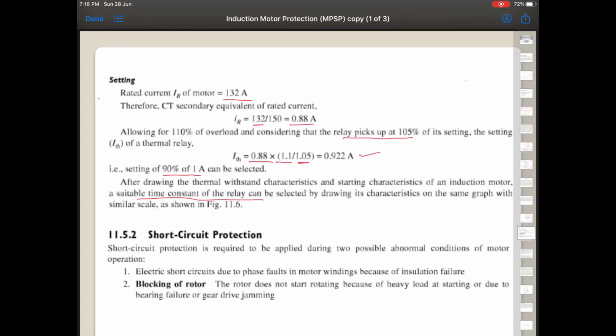As we know, if the rotor is not rotating, it means back EMF is not present, and I becomes equal to (V minus EB) by Z. If the EB part becomes very small because the rotor is not rotating, then the value is V by Z, where Z is a constant. So if this negative term is not present, if EB is 0, then you have a very high current. So we have to protect against this high current.